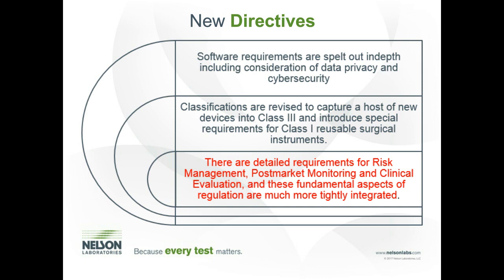We are personally seeing notified bodies require plans, even from device manufacturers that just did the checkbox mentality. In fact, a couple weeks ago, we had a client that just did all the testing per the chart and submitted it to the notified body. The notified body came back and said, why did you do this testing? Justify why this testing is performed. We need to see, and they even said, a biological evaluation plan to evaluate the risk of the device to justify why you did this test. So those endpoints are not checkbox. You have to justify why or why not those endpoints are needed for your device.